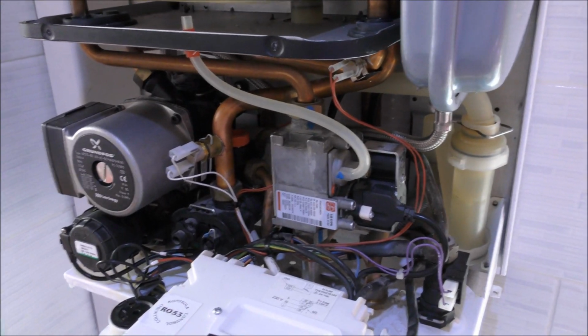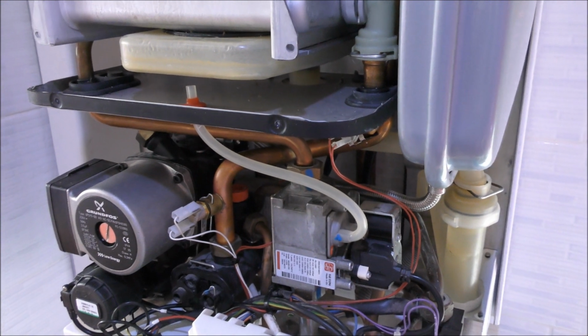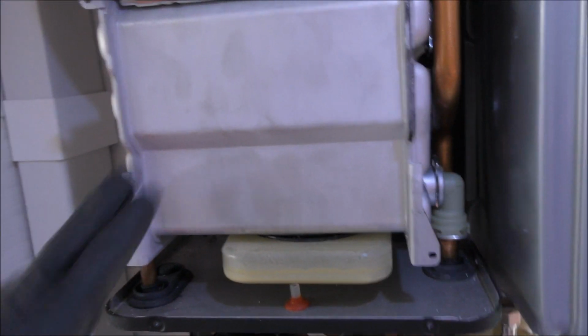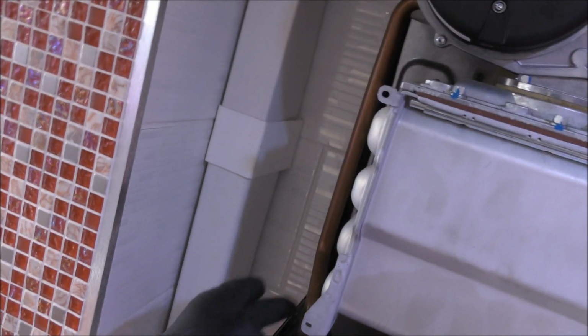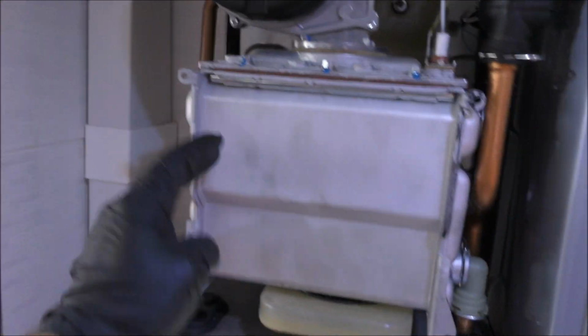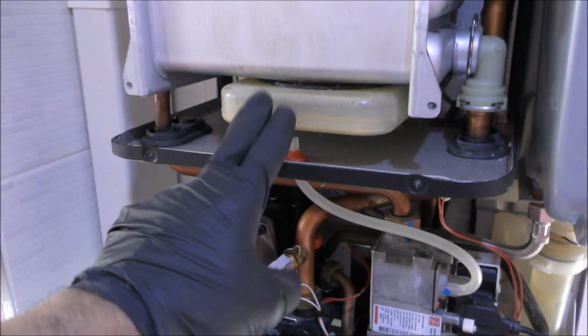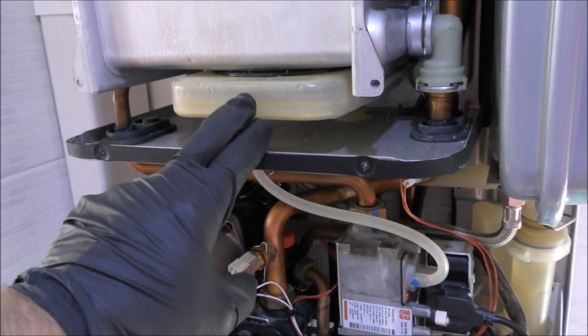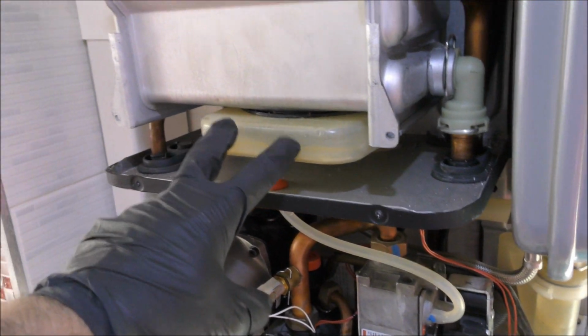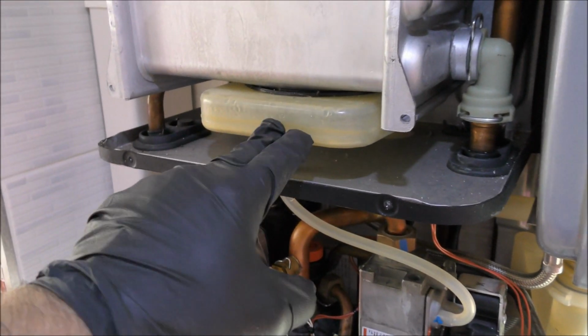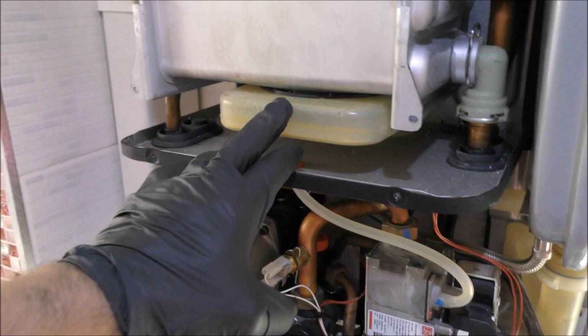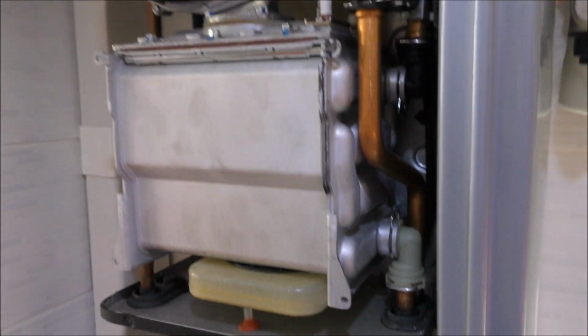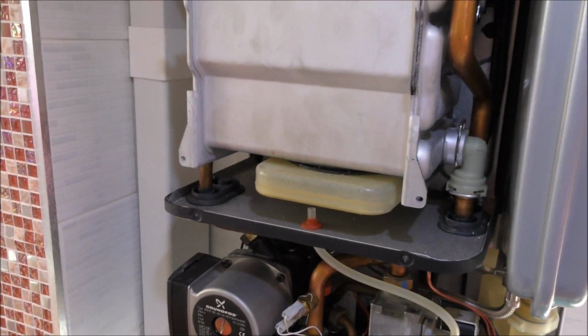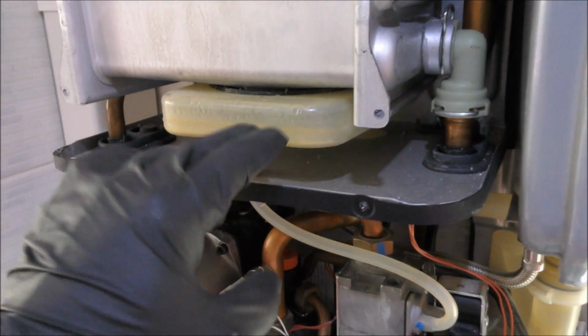Now, the other night when it stopped working, here's what happened. This is the main heat exchanger unit, with fans attached and gas coming in. This bit here is what was building up water, when normally it should stay clear with no water at all. The condensation goes through here, out into the flue and outside. So when the boiler is running, you'll see a little drip of water outside, that's the condensation going down and out.